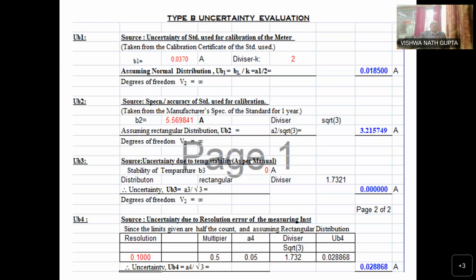So that is why, for precision equipment, we have Ub4, uncertainty due to resolution error. What is resolution error? After the decimal, how many digits the instrument can display, whether 3 digits, 4, 5, 6, 7, or 8 digits. That also has to be incorporated. Here this is the example of a 3.5 digit multimeter.